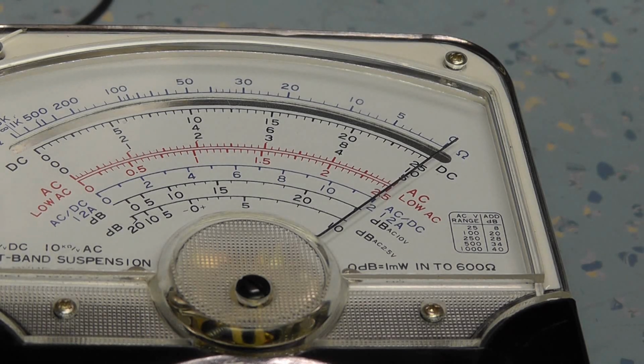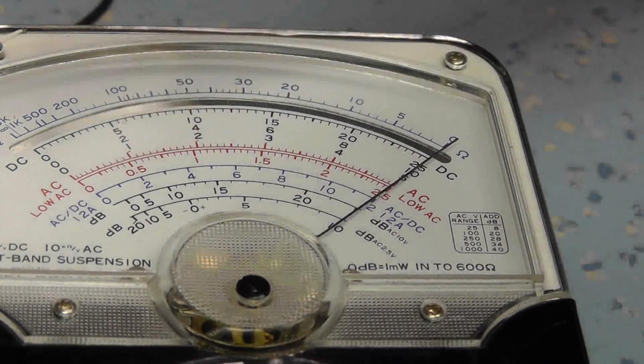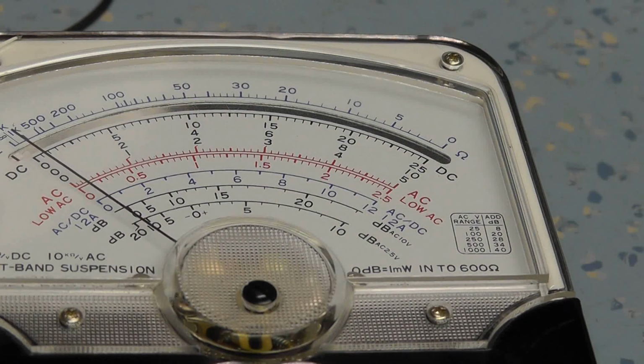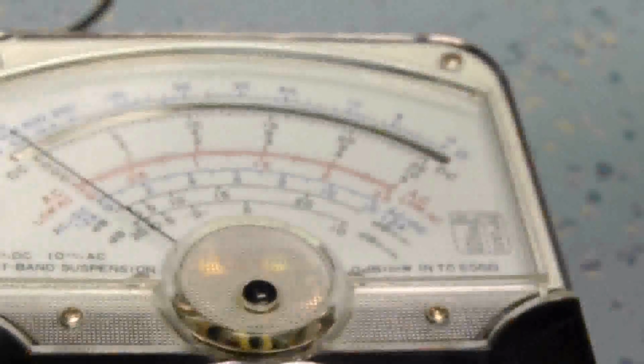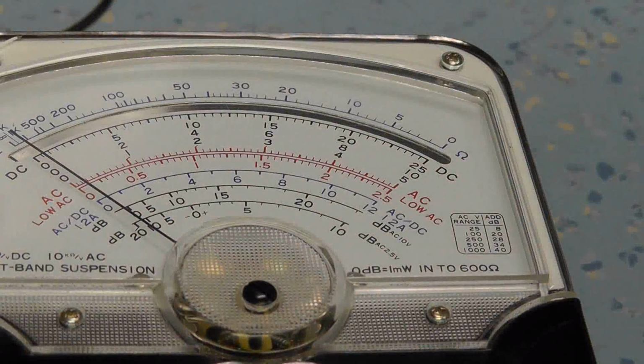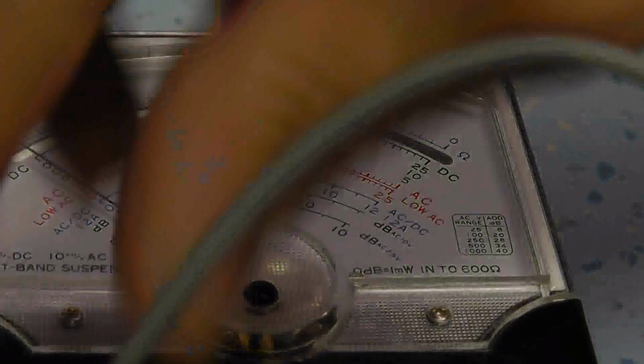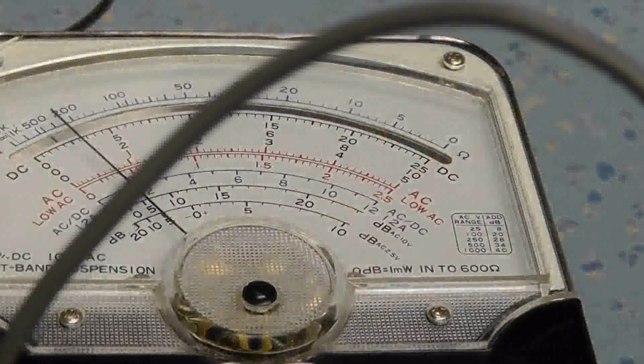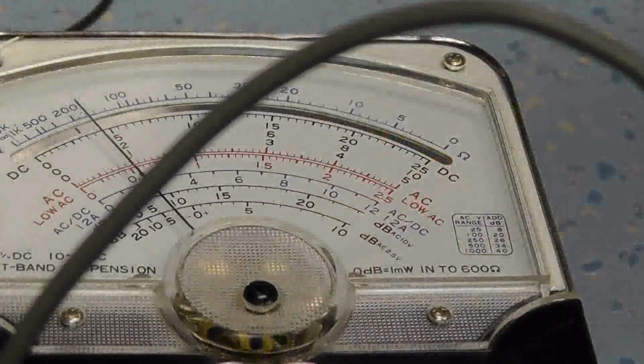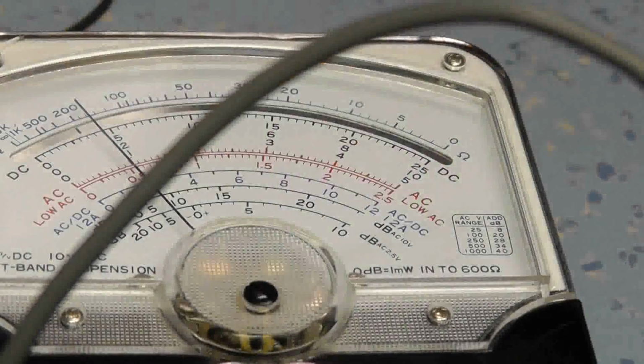So we'll try it on the 12 amp range, but this power supply can only give you 2 amps, but that should give us basically here. So let's try it on the 12 amp range. So what you do is you short my leads out, which I'm doing on the switch on the power supply. Let's give me 2 amps. So turn that to 2 amps and put it on the, where are we? Is there 12 here? DC 12 amps. So I need to go common on that connection and there. I got it around the wrong way. There you go. So this should be 2 amps. So 12 amp range is on the blue, 2 amps exactly.